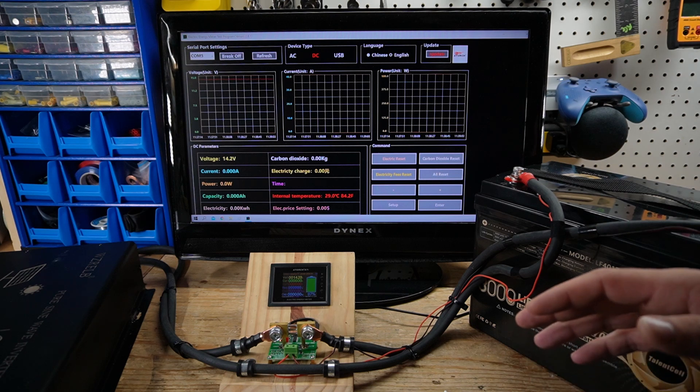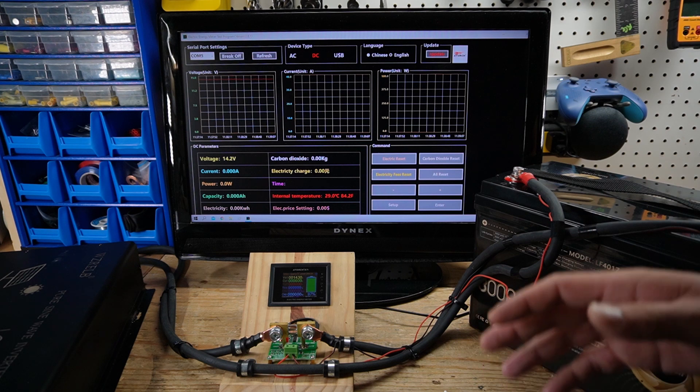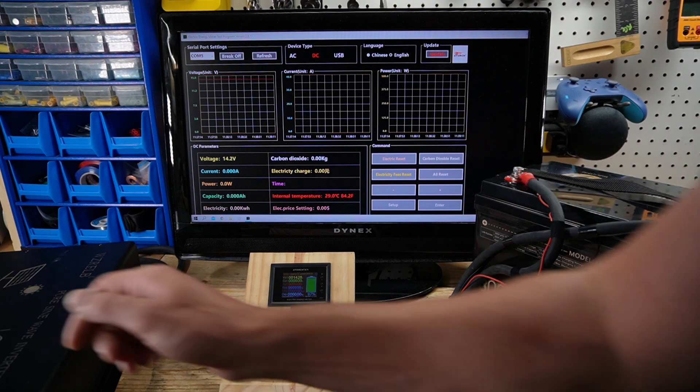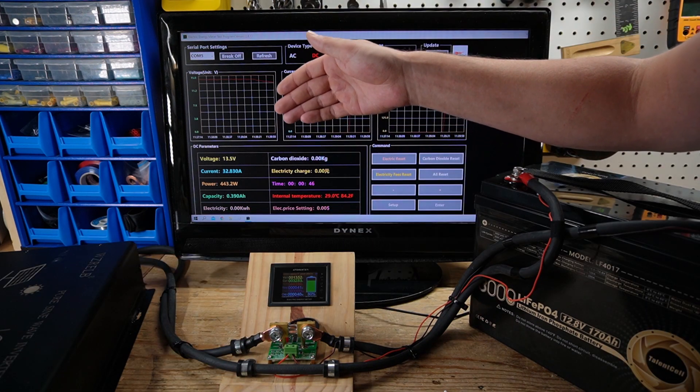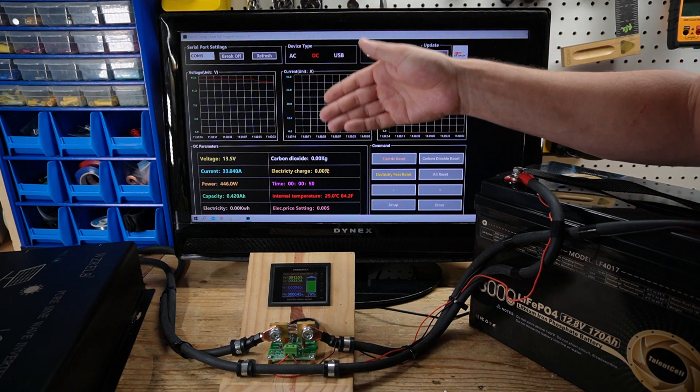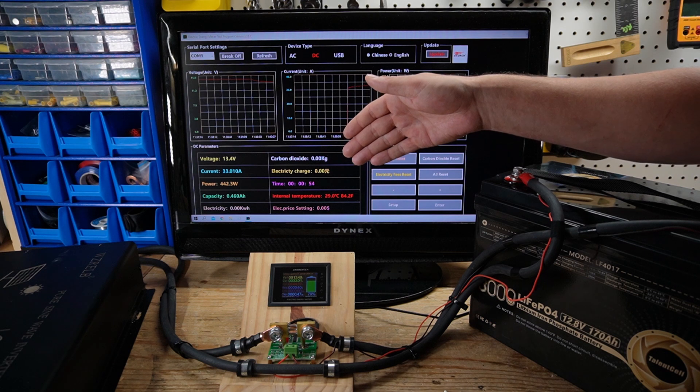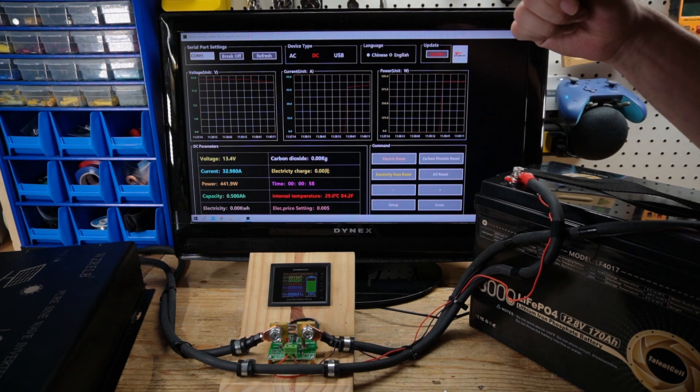I want to try and discharge around 435.2 watts in order to do a proper 0.2C discharge rate. So now we are discharging at 443 watts, which is as close as I can get it to a 0.2C discharge rate. I will let this test run. It should take about just under five hours, and we will be back with the results.